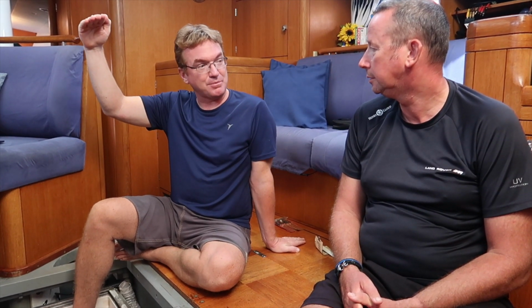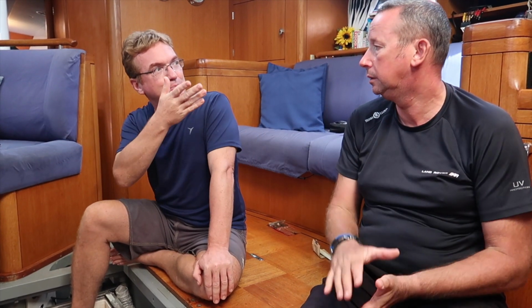Its amp hour counter needs to get to zero, and then it continues into the positives, and it keeps going into positives until the charging stops, and then it takes that as fully charged and resets to zero. But if you're constantly undercharging your batteries and it never gets to that point, it gets lost, and the percent state of charge becomes meaningless quickly.